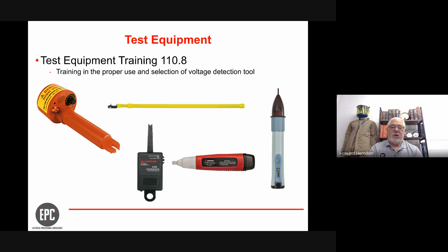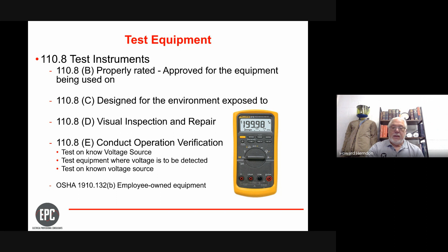Test equipment is another area that we can greatly affect. Making sure, and this is a challenge sometimes with union organizations because of the amount of tools that we as an employer have to provide versus what the employee provides, but making sure our people are using appropriate test equipment to make sure things are de-energized. Some of the areas that we can mainly affect are making sure they're properly rated, designed for the environment, and in good repair, and making sure we're using good, safe work practices: testing on a known voltage source with your voltage detection device or meter, testing the equipment where the voltage is to be detected, and then going back to that known voltage source. That'll make sure our equipment is properly working.